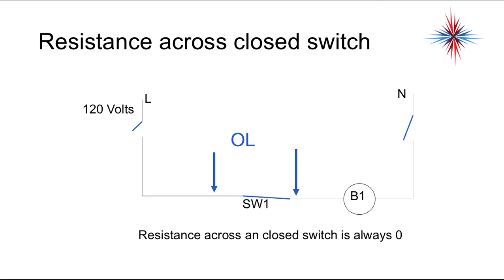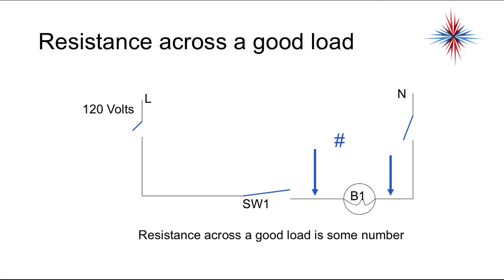So in this case, I'm reading OL. Okay, but it should be 0. Replace the switching device. Resistance across a good load is some number. It's all dependent on the load. Okay, it's some number. Resistance across an open load is going to be OL or infinite. OL just means infinite.